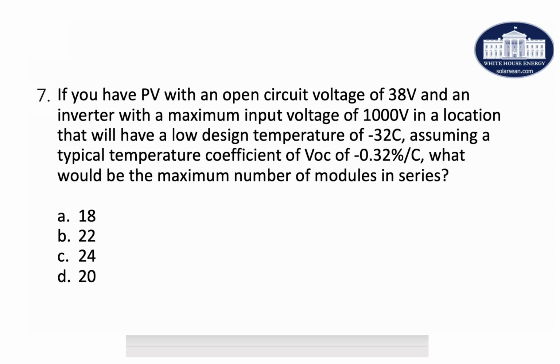a maximum input voltage of 1000 volts in a location that will have a low design temperature of 32 degrees below zero Celsius, assuming a typical temperature coefficient of VOC of minus 0.32% per degree C, what would be the maximum number of modules in series?